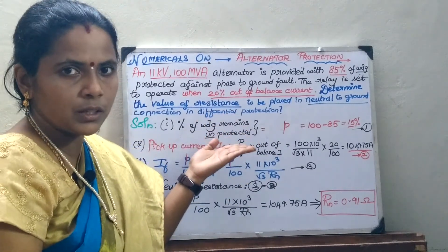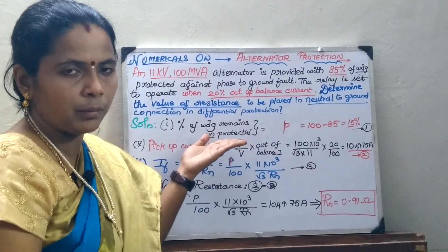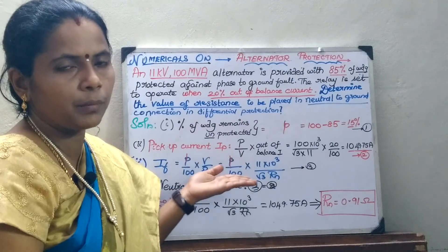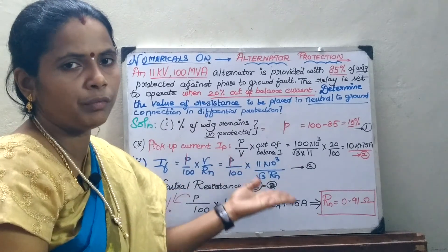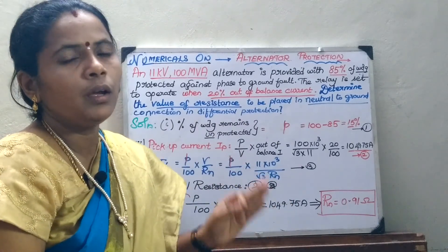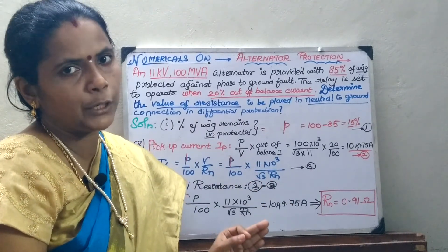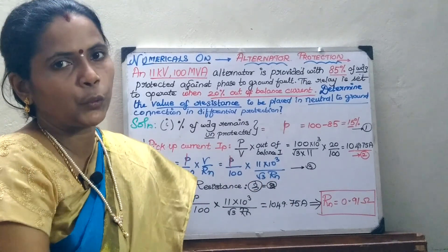So only four steps: find out the percentage of the winding that remains unprotected, find the fault current, find the pickup current, and equate them to find out your neutral resistance value. Thank you.